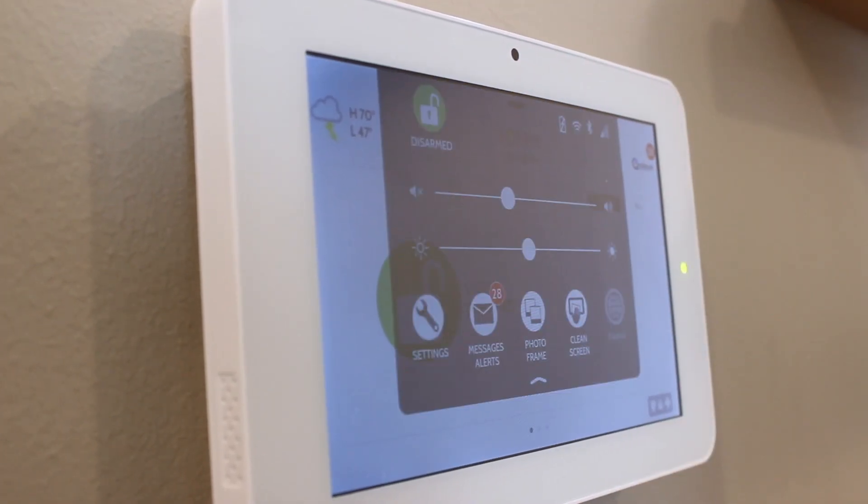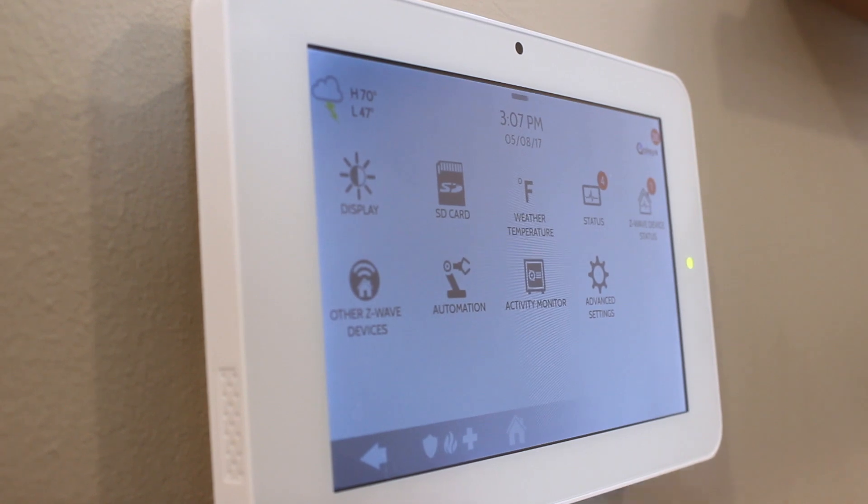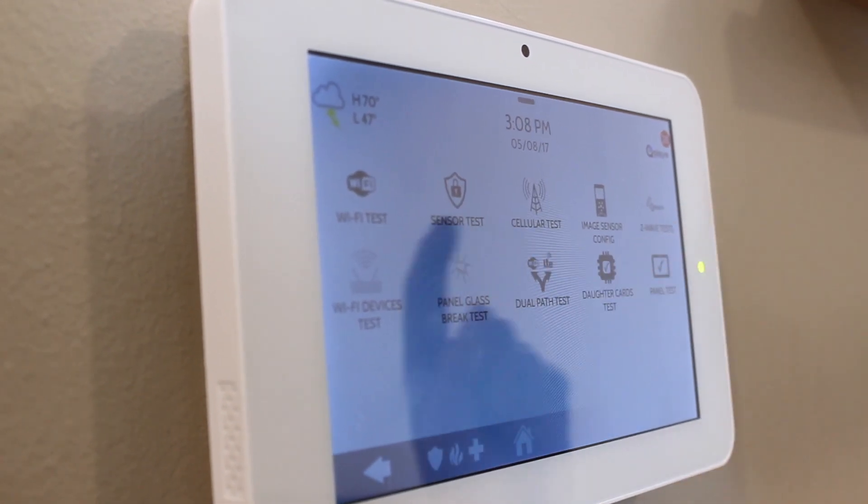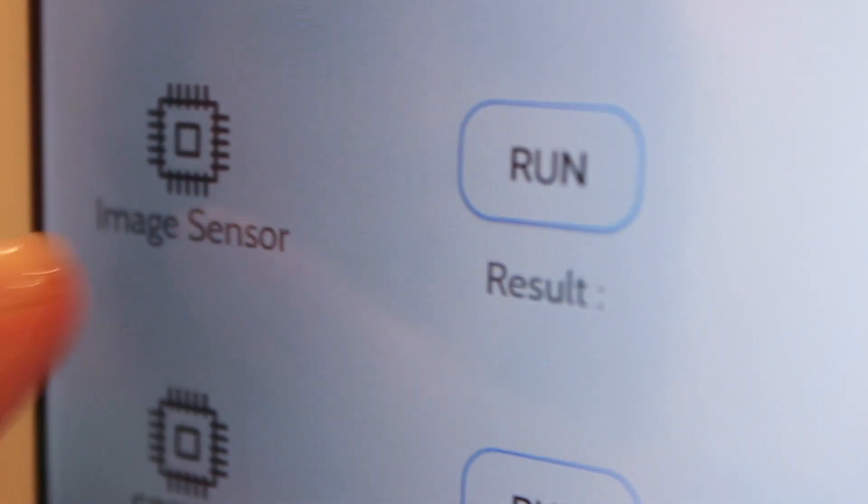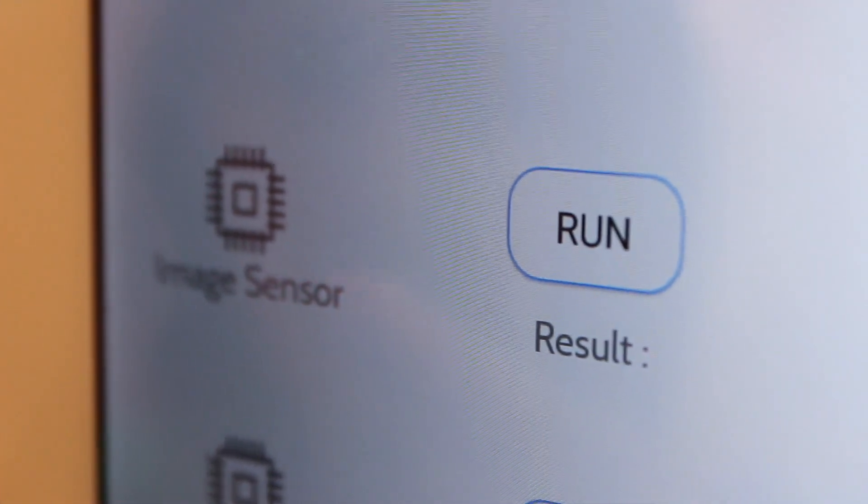To verify that it is working properly, go to settings, advanced settings, type in your code, go to system tests, and daughter card tests. The panel should show that the image sensor daughter card is installed.